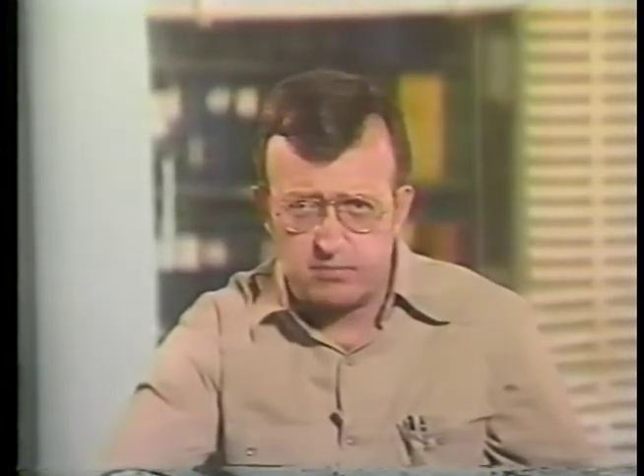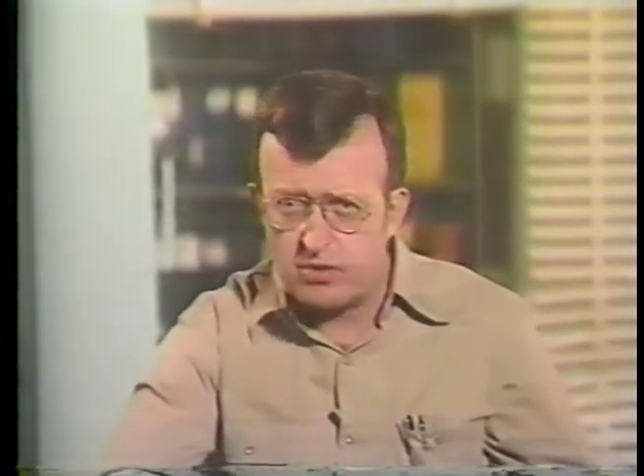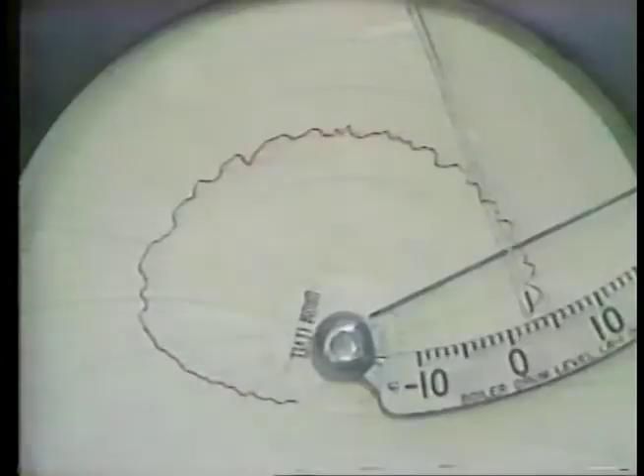Most procedures will indicate the ramp rate for boiler warm-up. Ramp rate means the change in temperature of the boiler per unit time. In the case of this boiler, temperature is increased no more than 150 degrees Fahrenheit every hour. This gradual increase is necessary to protect the boiler components from thermal stress.